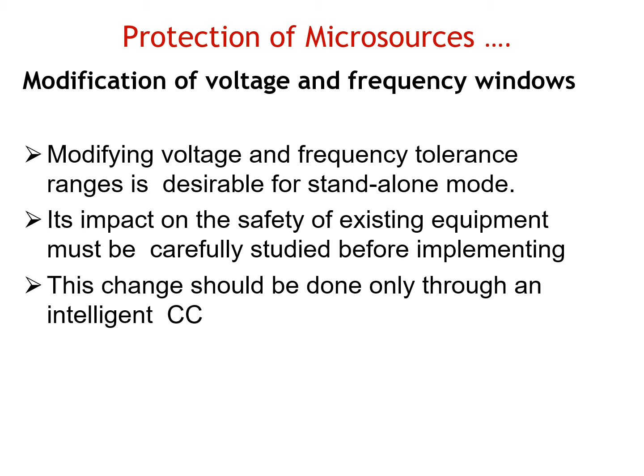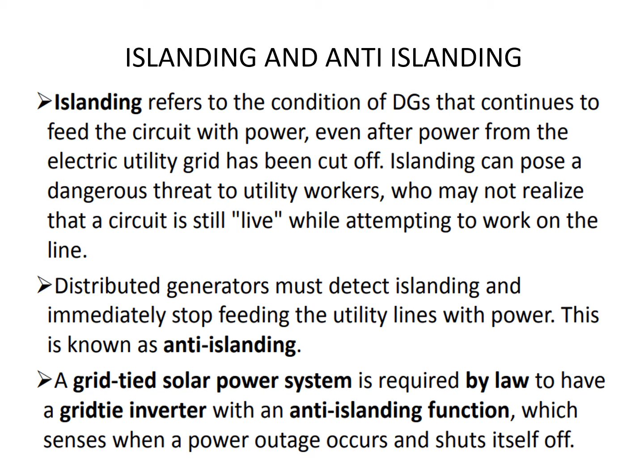So islanding refers to the condition of distributed generators that continue to feed the circuit with power even after the power from the utility grid has been cut off, and it may pose a dangerous threat to utility workers because they may not realize that the circuit is still live while they attempt to work on that line. And the distributed generators must detect this islanding and they should immediately stop feeding the utility lines with power, and that's called anti-islanding. So a grid-tied solar power system is required to have a grid-tied inverter with this anti-islanding function, and it should sense whenever a power outage occurs and shut itself off.